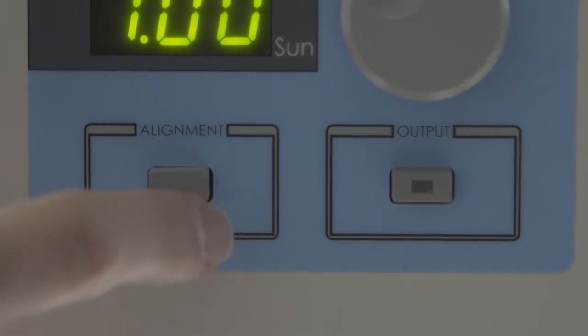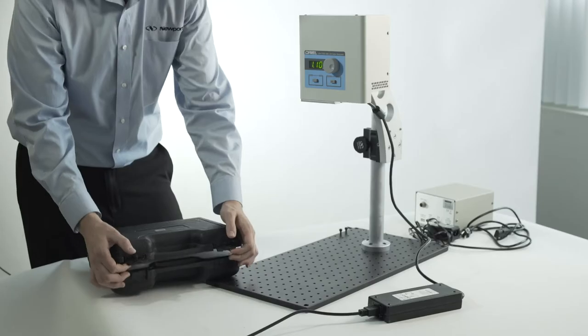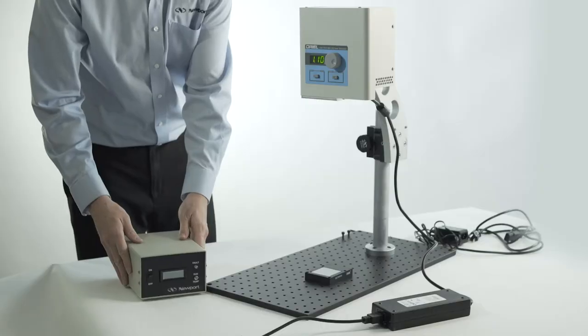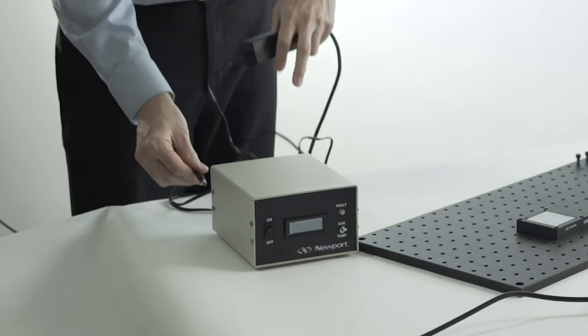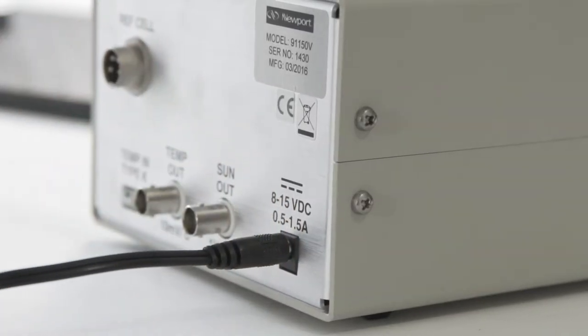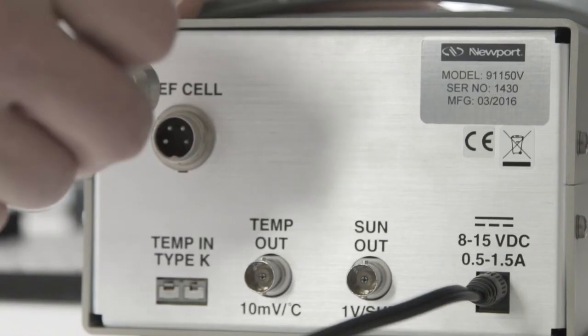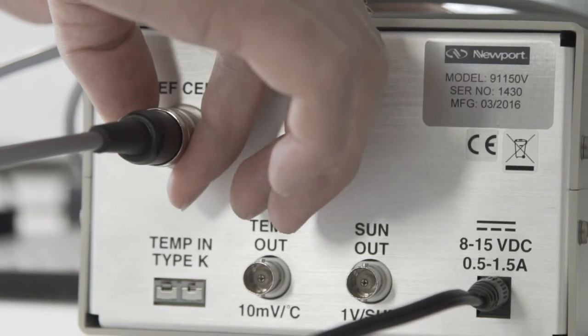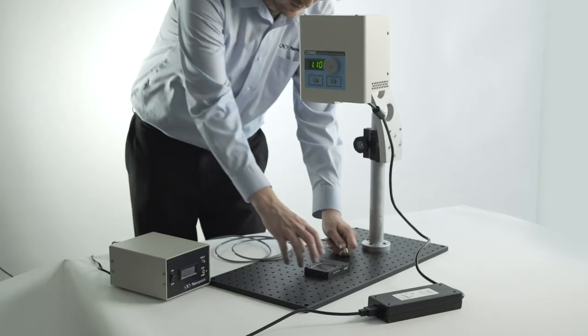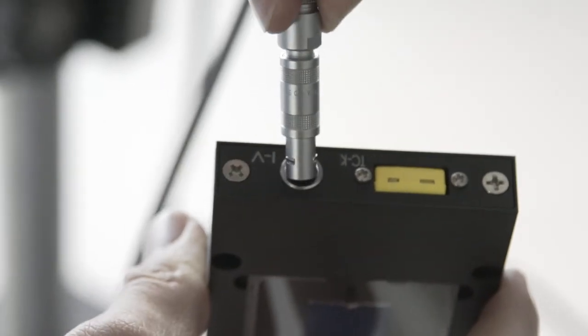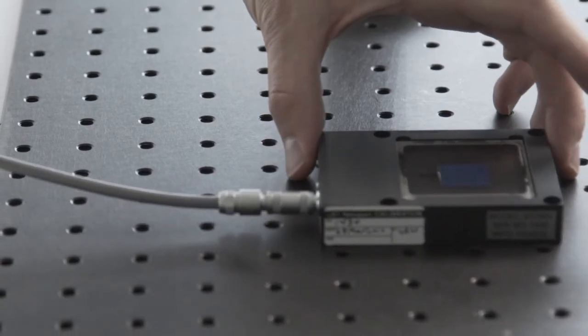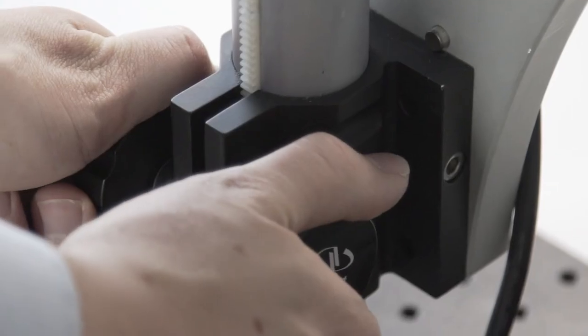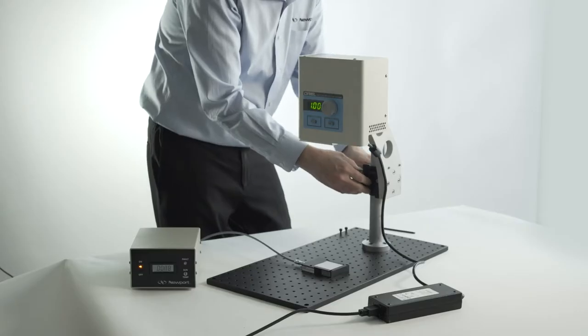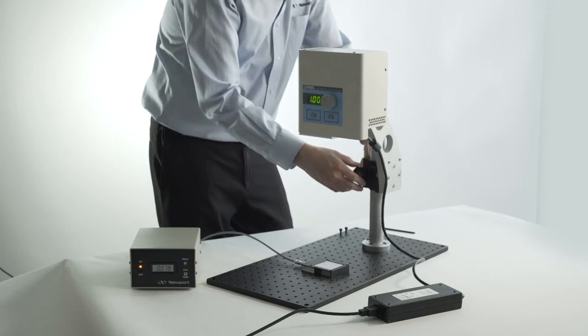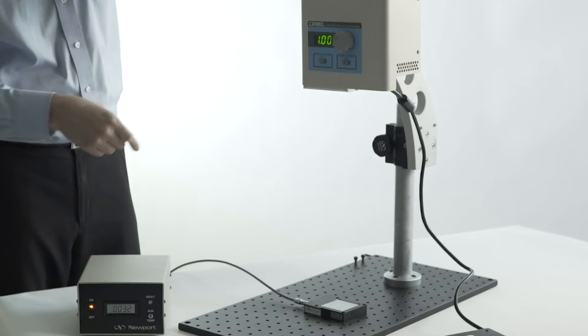In order to verify the appropriate working distance to achieve the one sun irradiance, connect the 91150V silicon reference cell to its meter and adjust the simulator to the accurate height. Now we can turn on the reference cell meter to verify the one sun reading. We can use the laser pointer alignment feature.